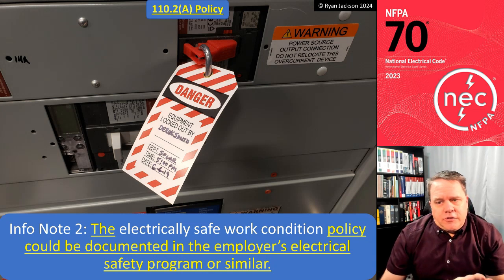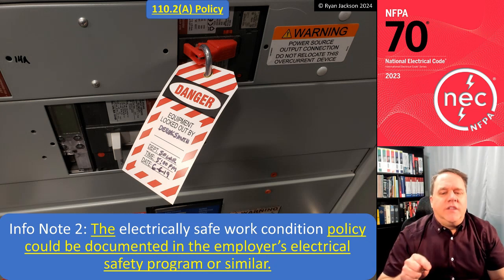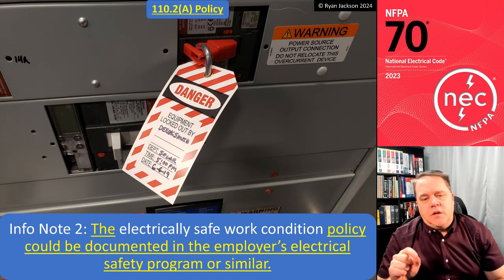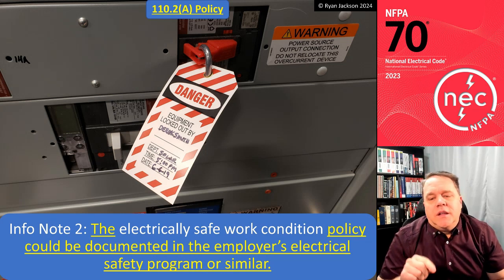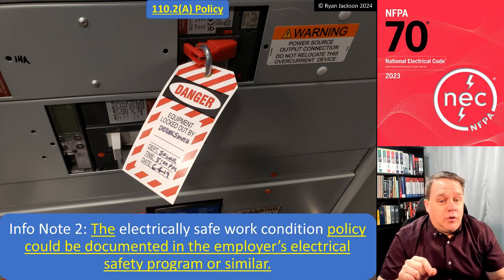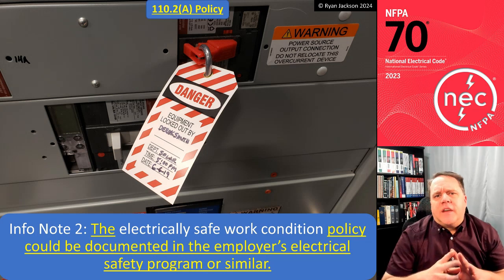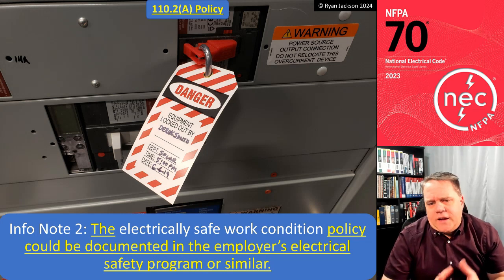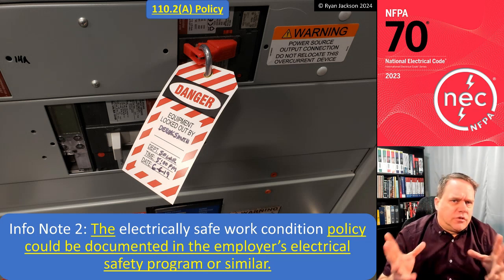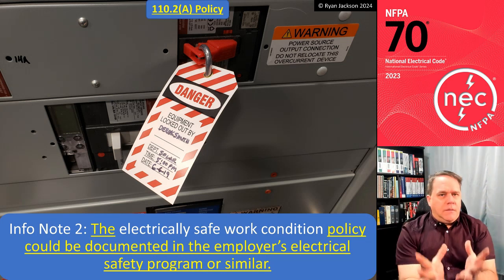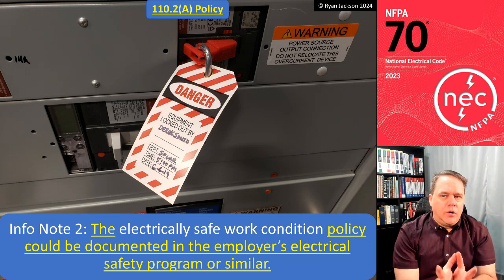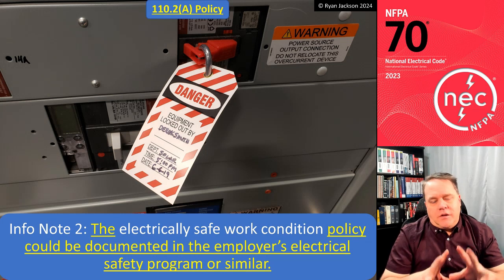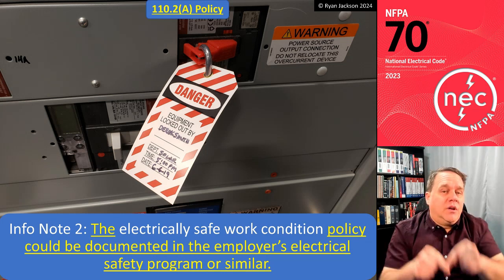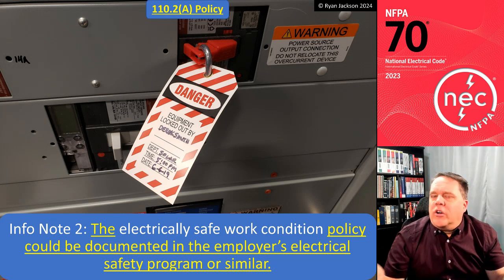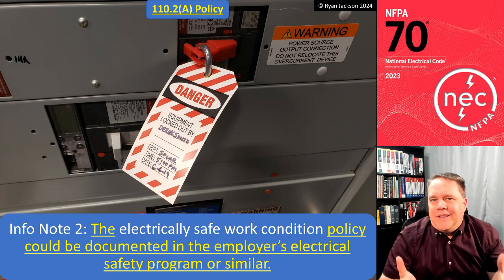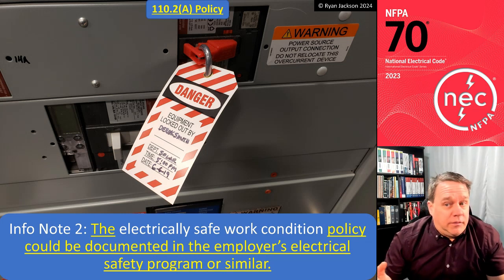There's another informational note here that says the electrical safe work condition policy could be documented in the employer's electrical safety program or similar. And I think that's usually where you would have it. Like I said before, you need to have an electrical safety program. That's the big picture, right? Within that program, you probably need to create the policy that we just discussed and put it in the program. I don't know where else you would document it if it wasn't in the electrical safety program.